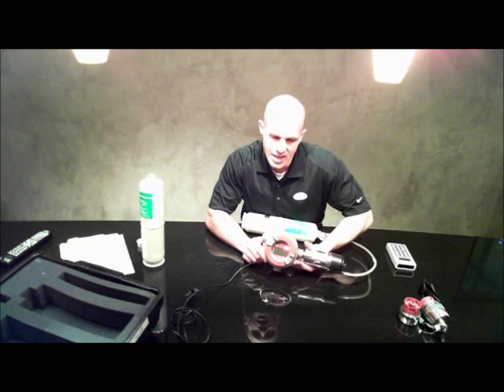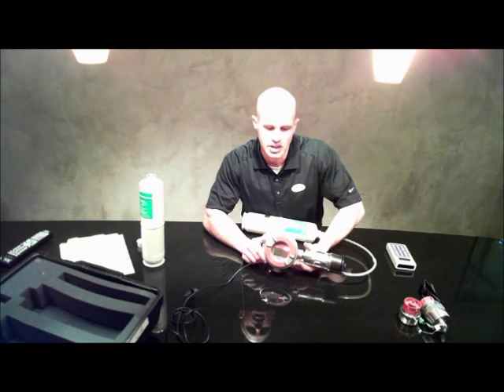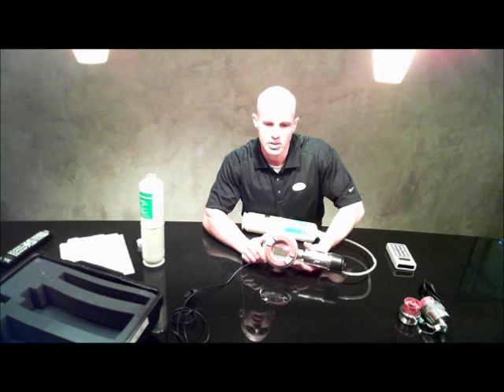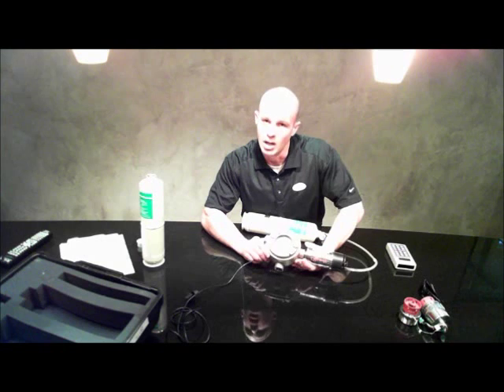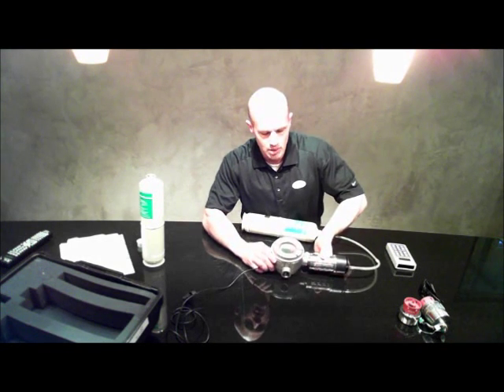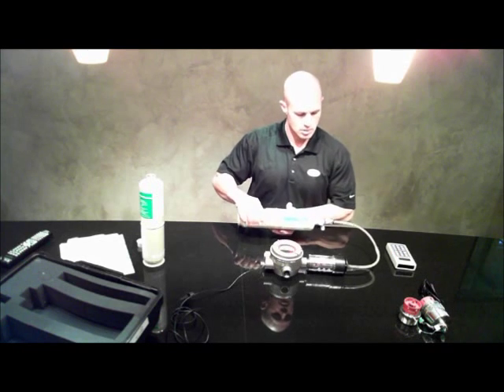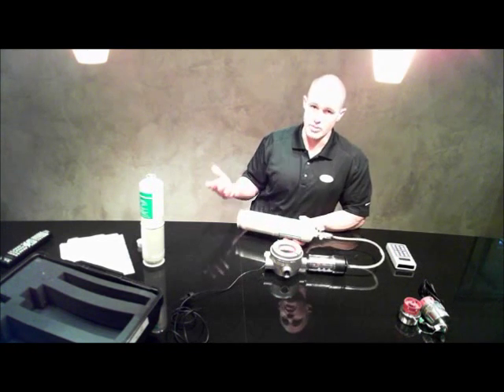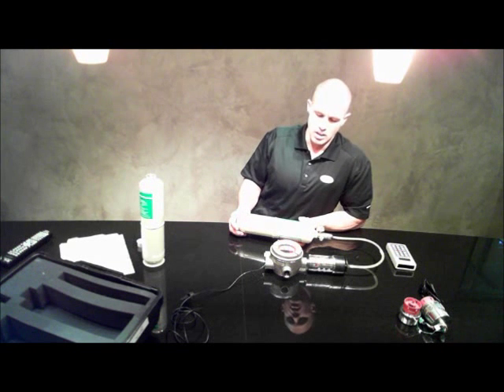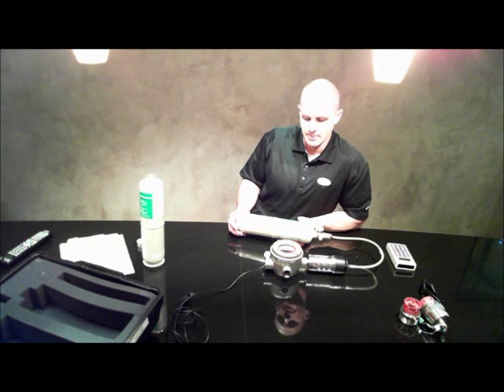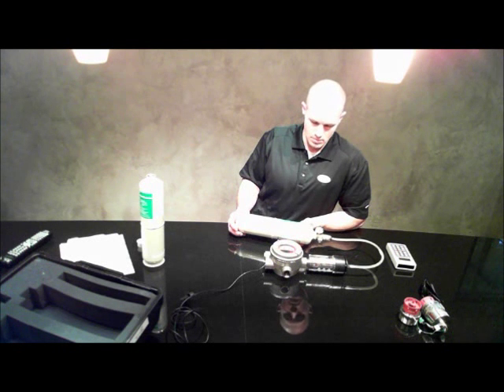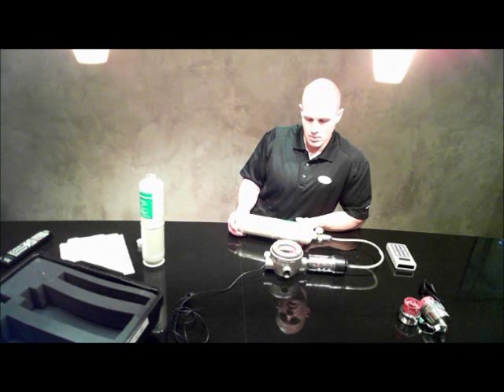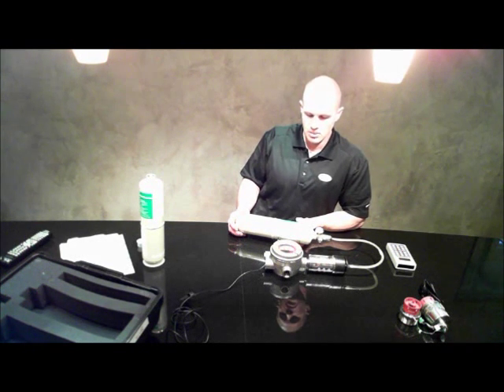So you can see it's got the red LED displayed right now showing that it's in a calibration mode. Anytime you get an alarm fault or any kind of fault condition, or if you're in a calibration mode, you'll have a red LED on there. When things are normal, it'll shift back to green. Again, this is about 30 seconds or so of letting the span gas flow into the monitor. We should be finishing up here in just a little bit.